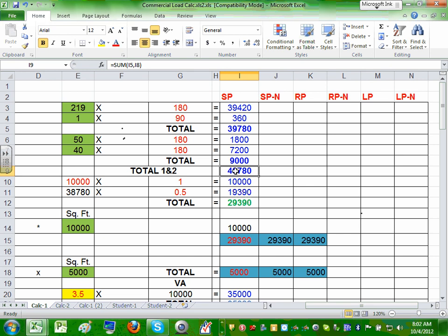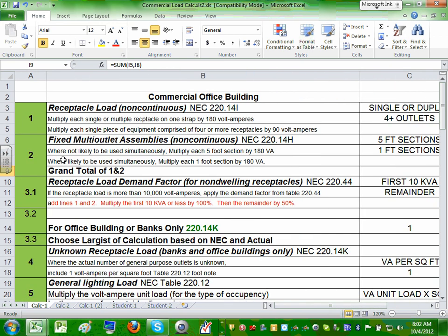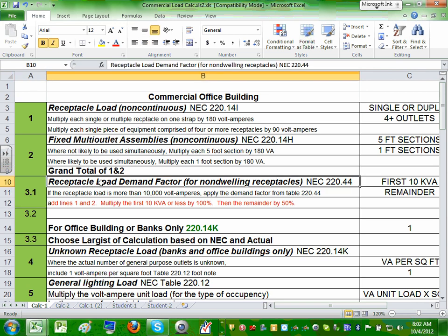You're going to be tested on this. If you get it now, you ace the test. Now that we have the receptacle load added up, step 3.1 for receptacle: you have to apply a demand factor. Article 220.44 requires you to apply a demand factor. The first 10,000 — leave them alone. Anything higher than 10,000, cut by 50%.